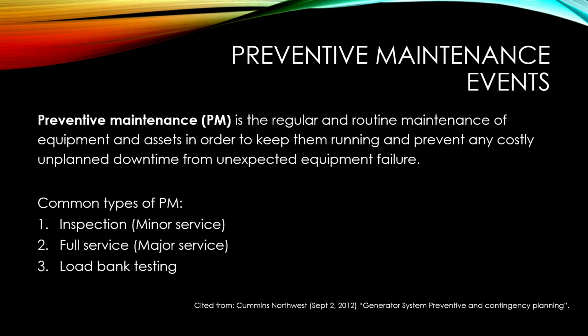The third type is load bank testing. Load bank testing will detect potential deficiencies in the system which may appear during extended operation, and will ensure full rated output capacity. It removes potentially damaging deposits, commonly referred to as wet stacking, in the combustion chamber and exhaust system, which may have accumulated under lightly loaded operation. It may be required annually by local code or regulation.